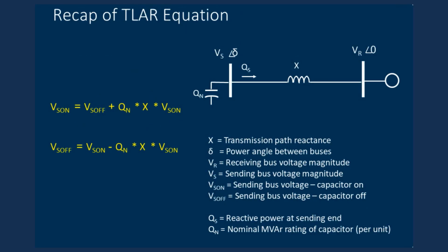So let's recap the TLAR equation for the voltage at the sending end of a transmission line that is connected to a generator that is regulating the voltage at that receiving end. So the path reactance is X, the angle between the buses is delta, the voltage at the receiving bus is VR, the voltage at the sending bus is VS. VS on is the sending bus voltage when the capacitor is in service. VS off is the sending bus voltage when the capacitor is out of service. The real-time reactive power at the sending end is QS, and the nominal megavar rating of the capacitor in per unit is QN.